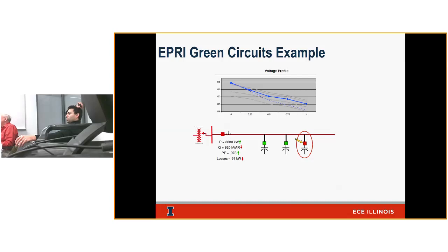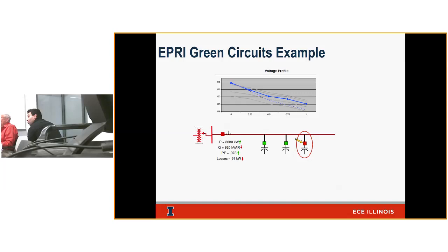Here's the first attempt: as soon as I close the cap bank towards the end, my KVAR absorption went less, power factor improved, and losses improved — went from 96 KW to 91 KW. The best part is my voltage profile went up. As I add VARs to the system I'm increasing the voltage, so the voltage at that last node went up. The real power also went up — because I reduced my losses, some loads will consume more energy.